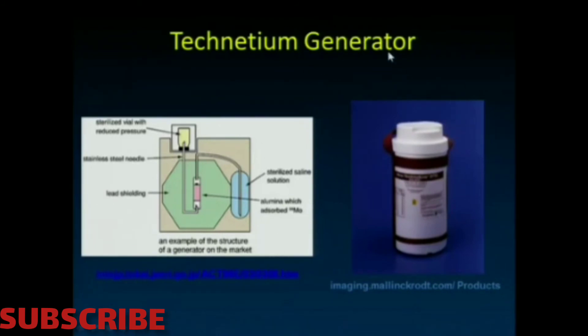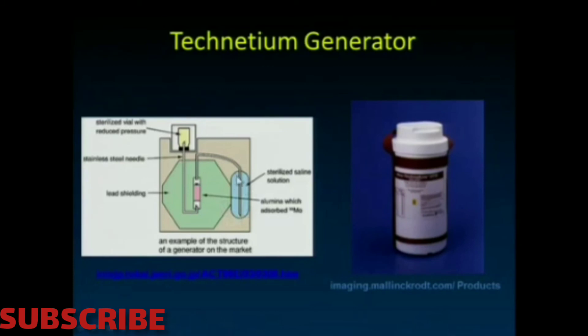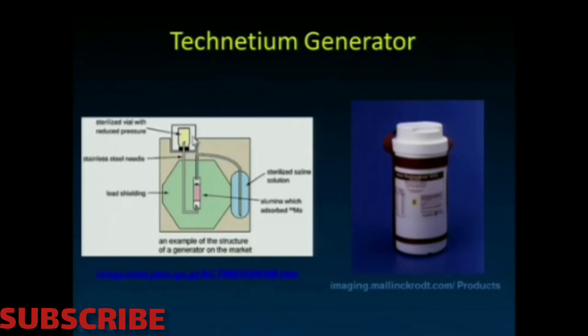We can get technetium fairly readily using a molybdenum generator. Here, alumina is loaded with molybdenum-99, and as it decays to technetium, the technetium becomes water-soluble. A sterilized saline solution is connected through that column via tubing, and if you place an evacuated vial onto the needle at the top, it sucks the fluid past the column, taking off the soluble technetium into your vial — hopefully with minimal breakthrough of molybdenum.